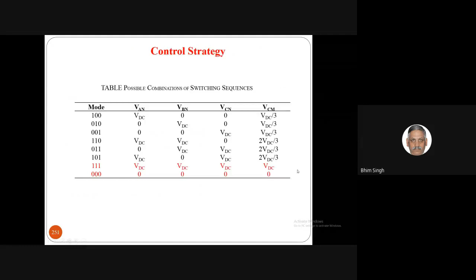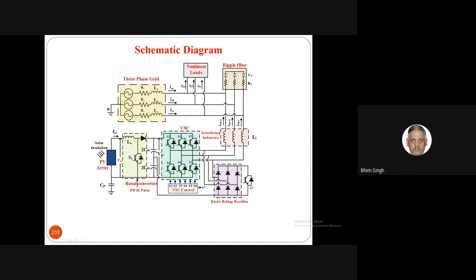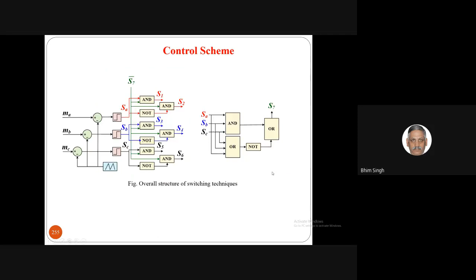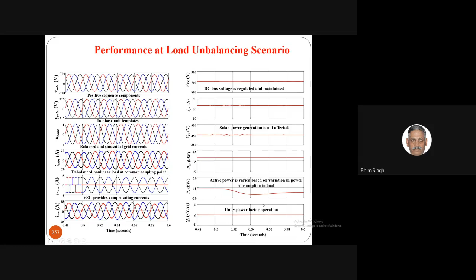By adding two additional vectors in the inverter switching and modifying the control, along with adding this circuit, we are able to further reduce the leakage current through this additional circuit and by modifying the control of this H7 switch in coordination with the inverter switches. These modifications add additional vectors into the inverter switching to reduce leakage current.